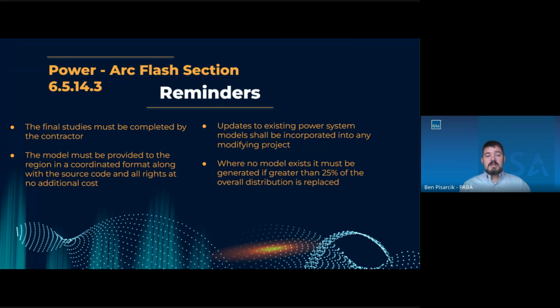Updates to existing power system models must be incorporated into any modifying project. So if you're touching the electrical distribution system and you have an arc flash study that's been done recently, please include funding in there to have that updated. It's a requirement of NFPA. Where no model exists, if 25% of the distribution is being affected, then a model must be generated. So again, funding must be there to generate that model for that particular upgrade.